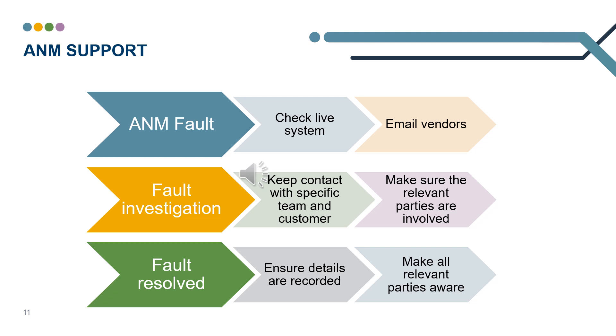If the network is intact, I will run through some data to analyse when they issue occurred, and then I will go through our dedicated process which involves speaking to internal teams such as IT or real-time systems, and our external vendors such as our support engineers. They will be asked to investigate and will use live and historical data. They will keep in contact with myself and the support team with updates and possibly ask us for further information. They may ask that we send someone to site to investigate or fix the issue — in this case, we use our SSE network engineers near site. Sometimes we might email the customer to see if there are any works on site or if they are aware of an issue. Once a fault has been resolved, we will make sure to keep a record of the incident and the resolution, and make all relevant parties aware and contact the customer.